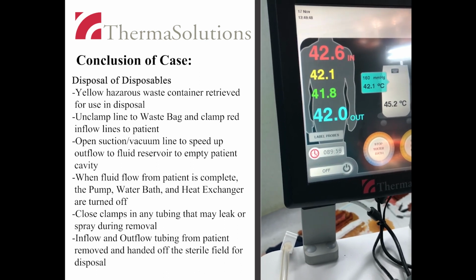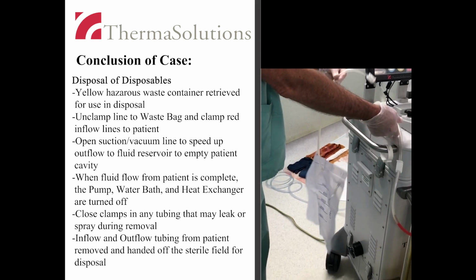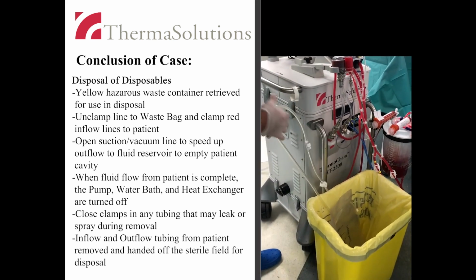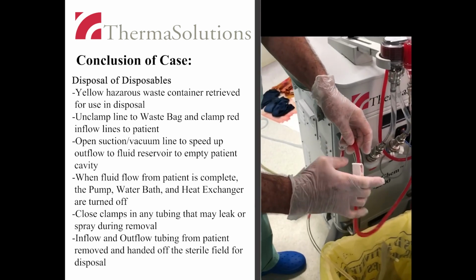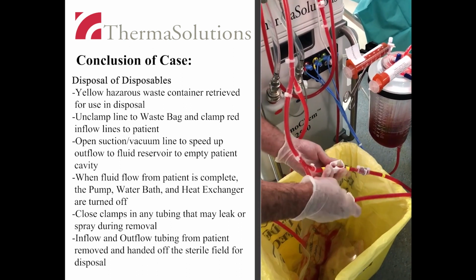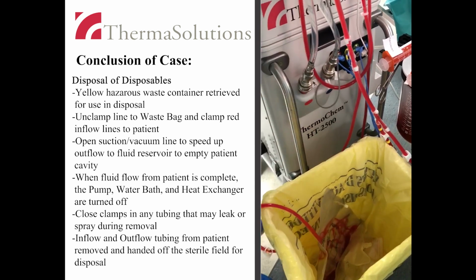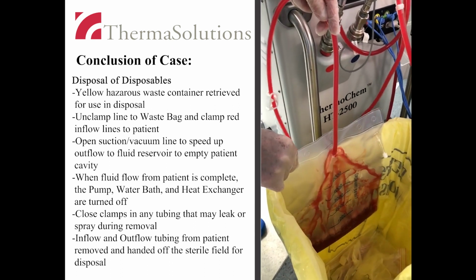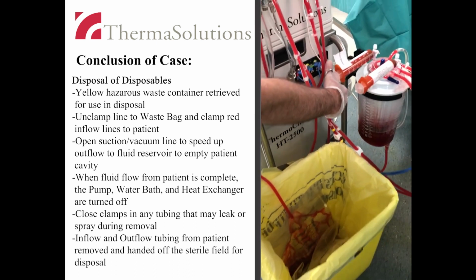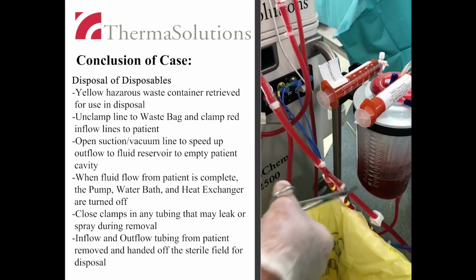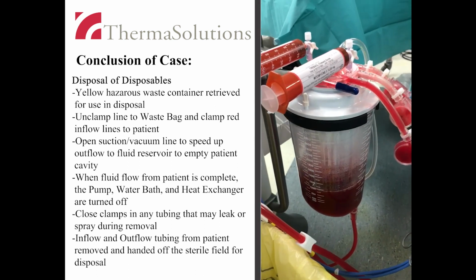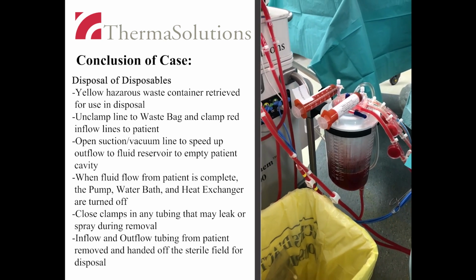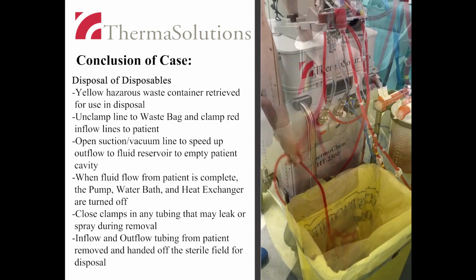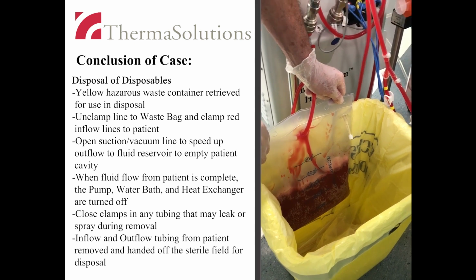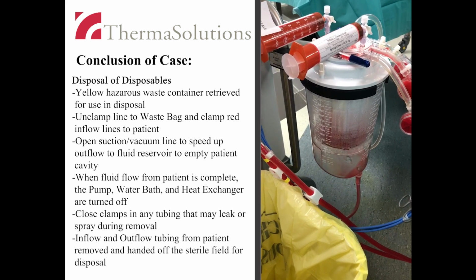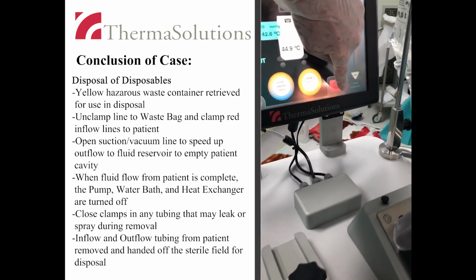At the conclusion of the treatment, a hospital-approved hazardous waste container is utilized for disposal of the tubing and fluid. Unclamp the line to the waste bag and clamp the red inflow lines to the patient. This will direct all flow to the waste bag. In an open Coliseum technique, suction or vacuum can be applied to the disposable system to speed up outflow to the fluid reservoir from the patient cavity. When the fluid flow from the patient is complete, the roller pump is turned off.